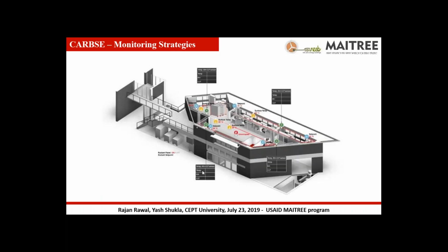This is another screenshot of the building management system, where you will see we have temperature, relative humidity, and also the carbon dioxide level in the space, so that we can effectively control the carbon dioxide level by operating the ventilation fans as needed. This has worked very well in effectively managing only the outdoor air quantity that we need for the building.